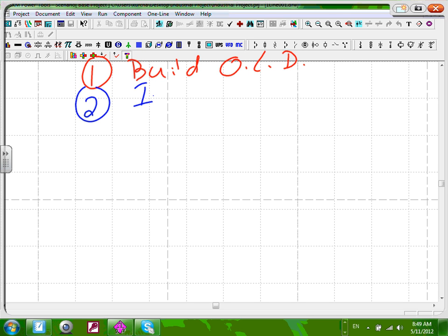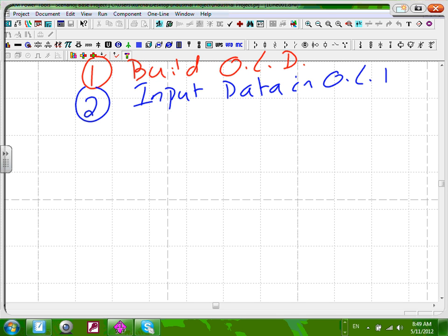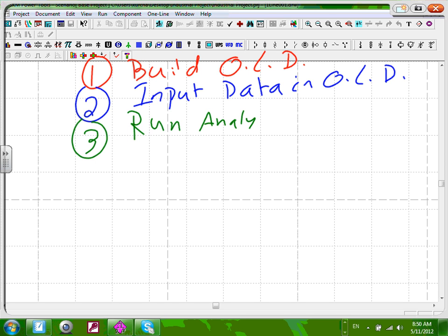Step two: input data. Unlike CAD, every time you put a cable or a transformer, you have to populate the electrical data in that component. So first we build the one-line diagram — it looks like the riser you guys did with us. Then we need to populate the data, input it into the one-line diagram. Step three: when we build the one-line diagram and put the data in it, you run analysis.